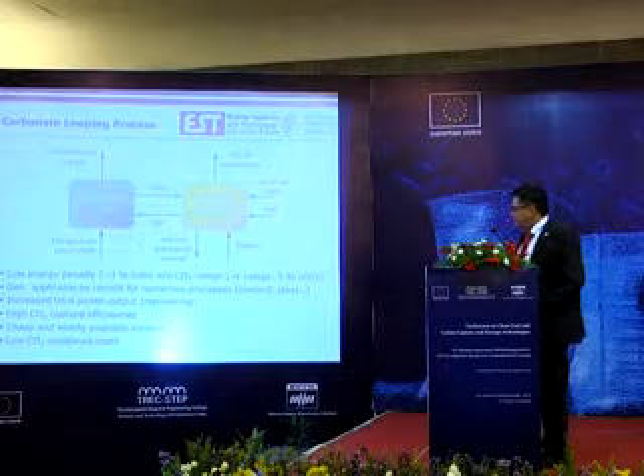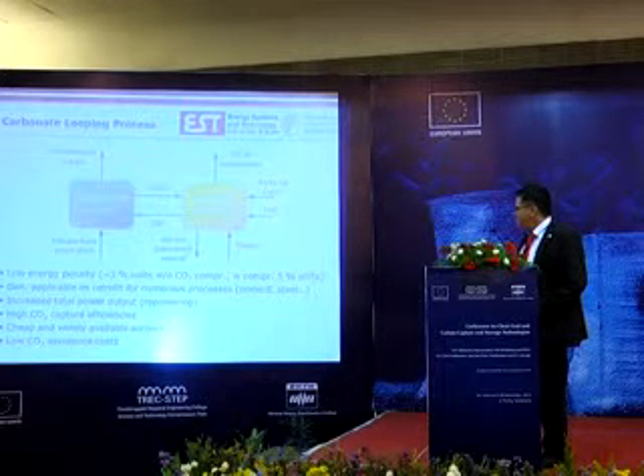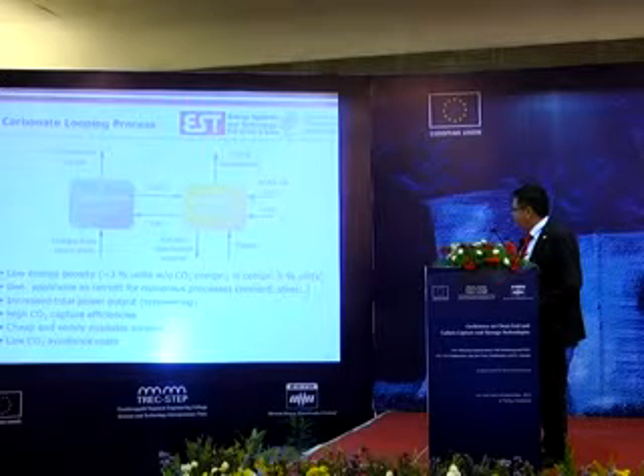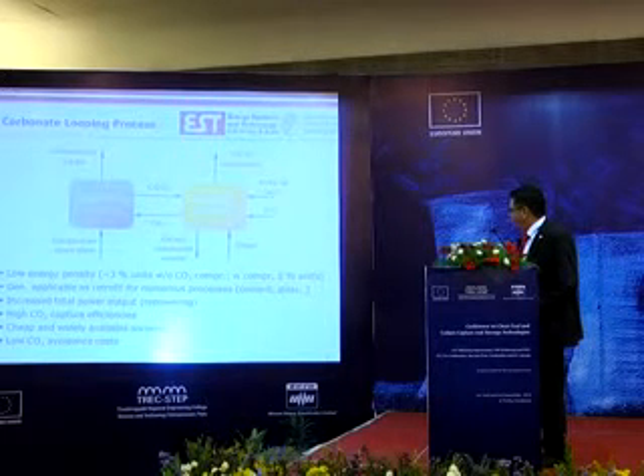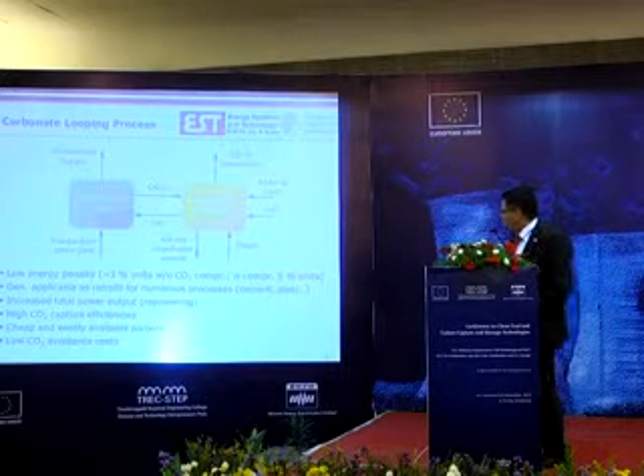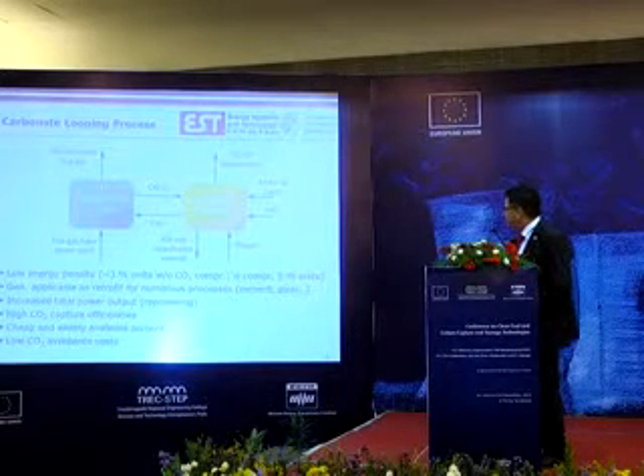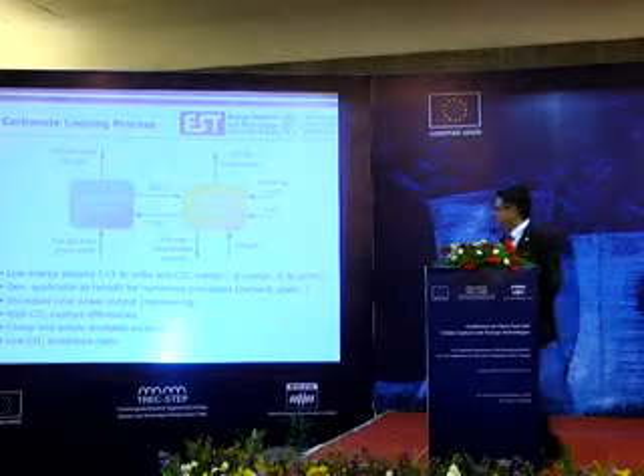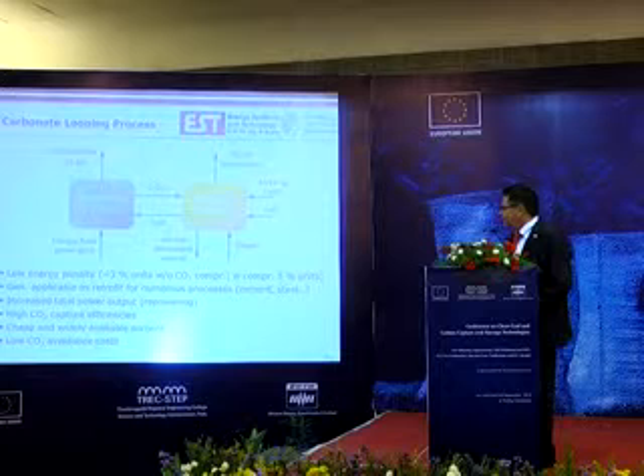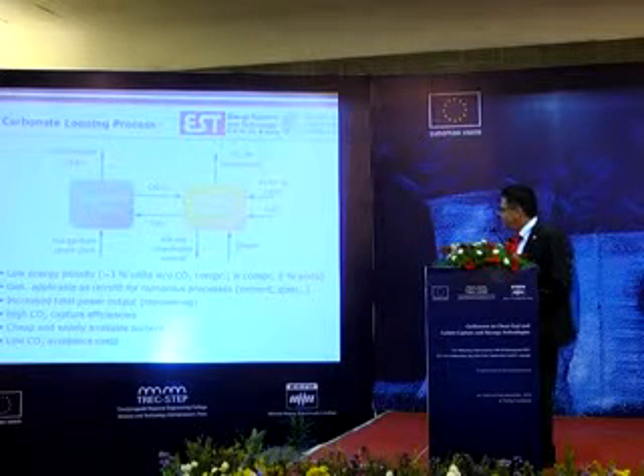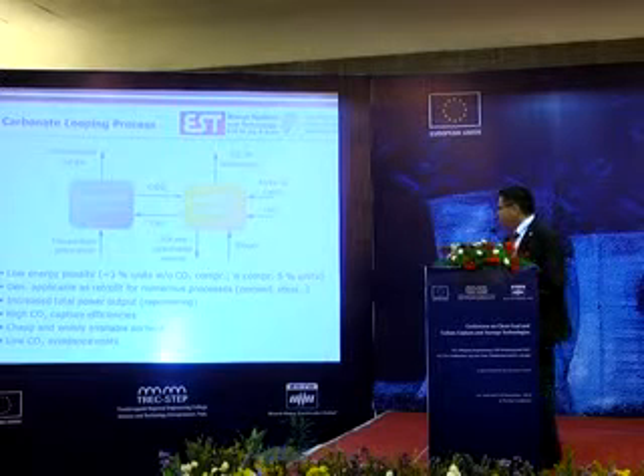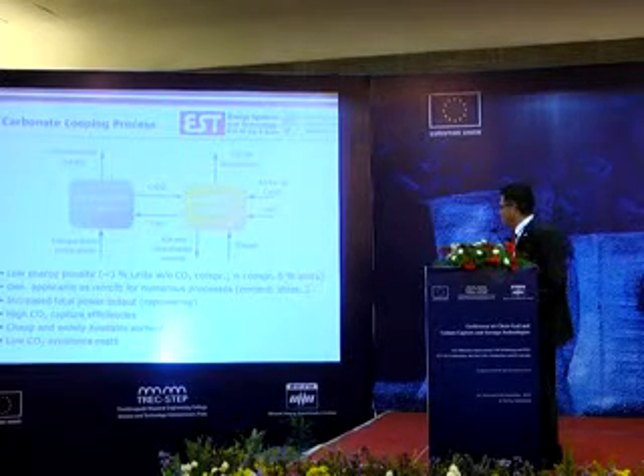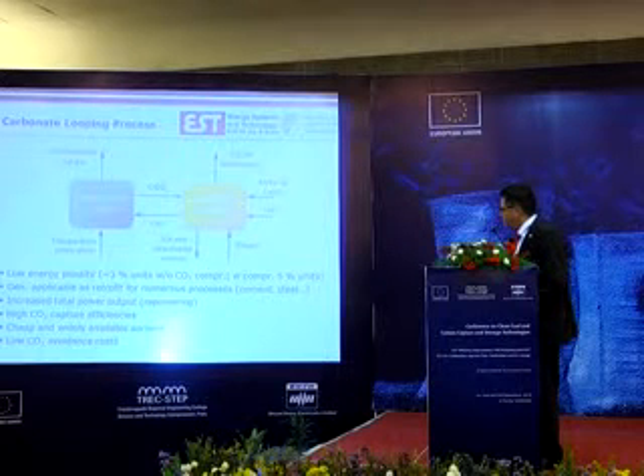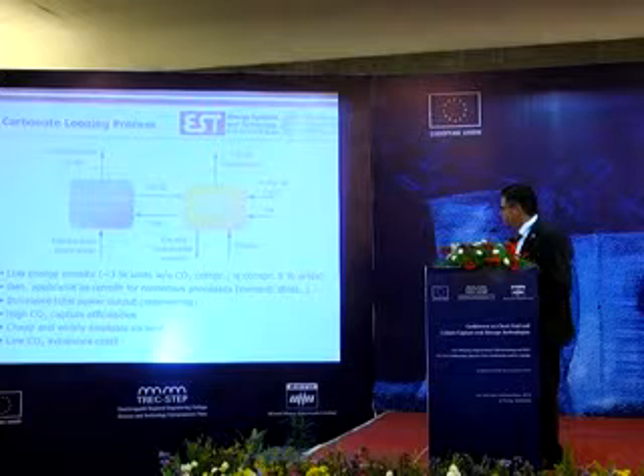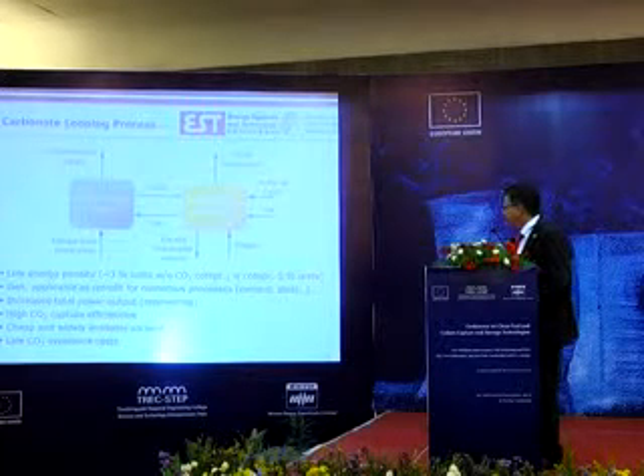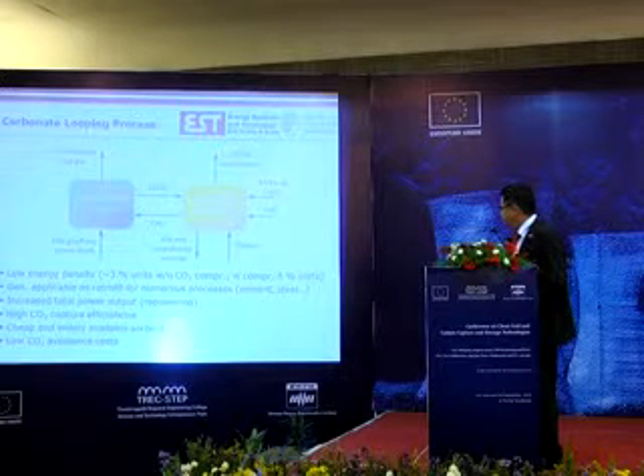The features of the process are shown here. There is a low energy penalty. We need only a third, that means 30%, of the oxygen consumed in an oxy-fuel plant. Only a third of the oxygen demand. That means we have a much lower energy penalty. The efficiency decrease will be only 3% units without CO2 compression, and with CO2 compression it comes to a figure of 5% units. If you have in mind the figures for MEA and oxy-fuel, with efficiency penalties above 10% units, we are 50% lower.